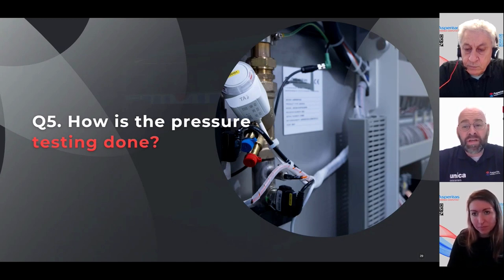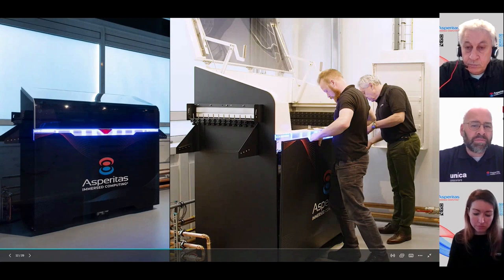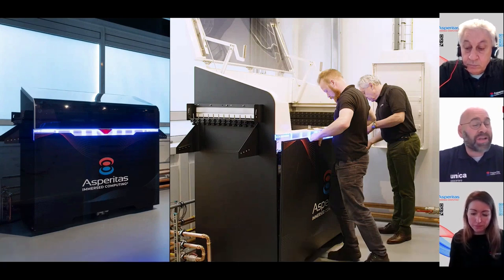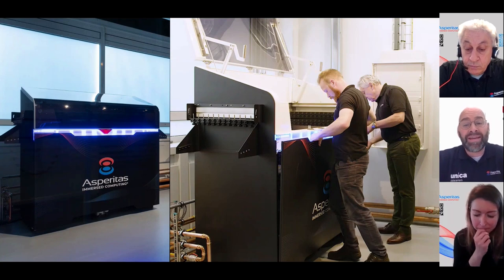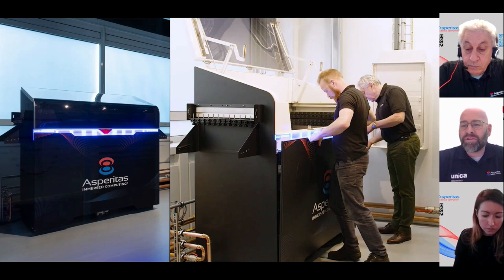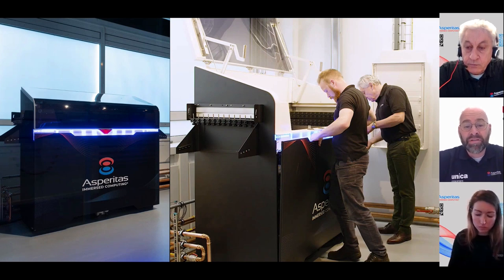What we have done as Unica is we adapted the data center industry standards for commissioning processes already 4 years ago. Customers will surely recognize commissioning steps like the FAT, the factory acceptance test, but also the SAT, the site acceptance test. As part of this testing methodology, we also do quite intensive pressure testing of the cooling system. Of course, we start with the FAT, where the system will be fully pressurized and tested in the production facility, like Hamza already mentioned, and that will be done under controlled circumstances.